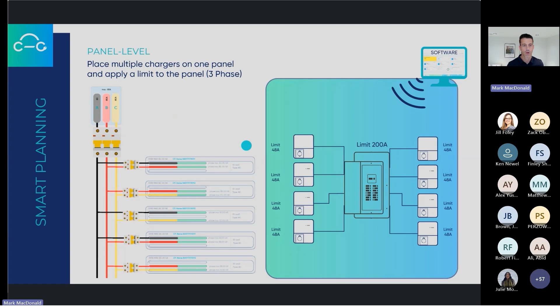Now, I mentioned these chargers are single phase, but of course, multi-unit residential buildings are primarily 3-phase systems. So this is a panel level load share on a 3-phase 208 volt panel. This is actually a visualization from our back end. Now we can connect chargers to phase A, so rotation AB, phase B, rotation BC, and phase C, rotation CA. And now, instead of overloading the branch circuit at that 4-to-1 ratio, I can overload the main on the panel at that same ratio. So now I'll put 800 amps of charging load, use up all those circuit positions in my 208 volt panel, and I'll overload the main from 200 to 800 amps in that same 4-to-1 scenario.